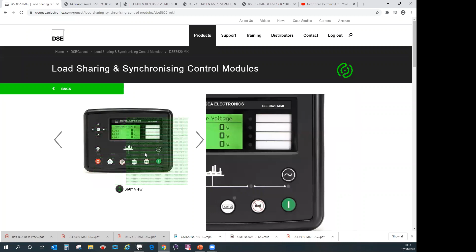The reason we have that is if you've got a site with a long-term application, you probably don't want people pressing the open and close breaker buttons all the time. It's probably safer to say, press the test on load button, press the green button, and the generator will start and then go on load. You don't need to do anything. When you're finished, you just take it out of test on load, so you put it back into manual mode or back into auto mode, and the generator will go off load. So it keeps it simple.